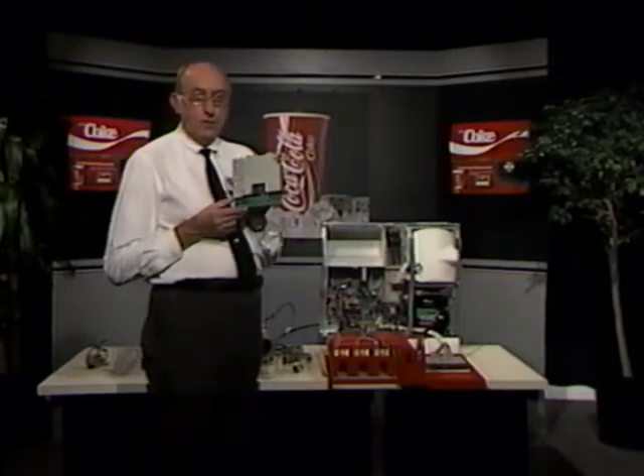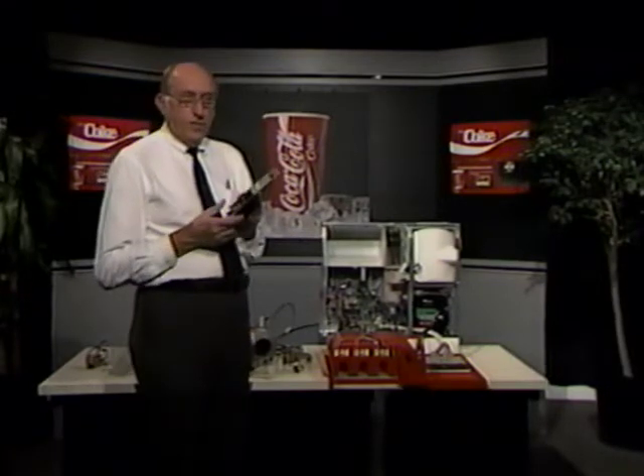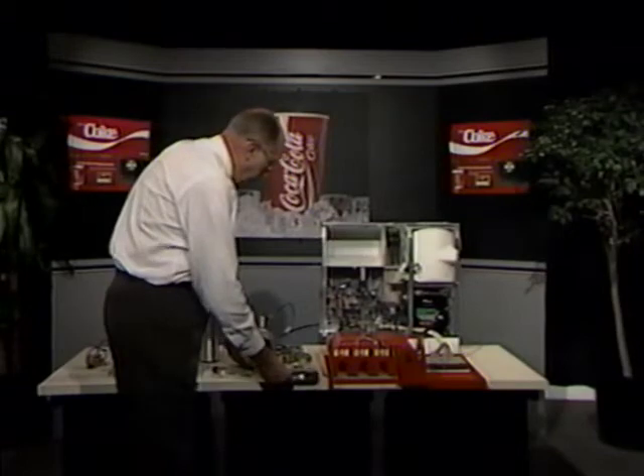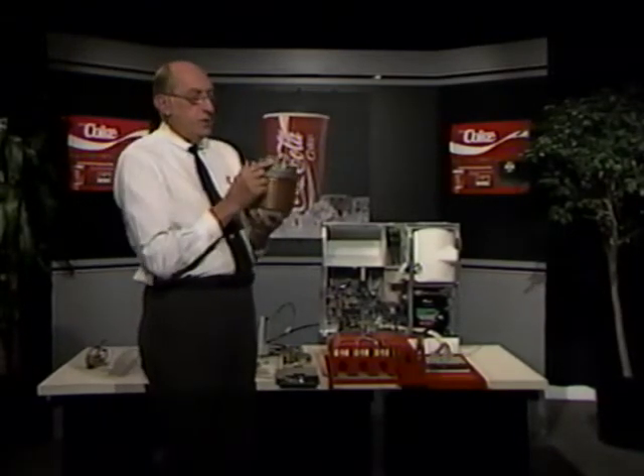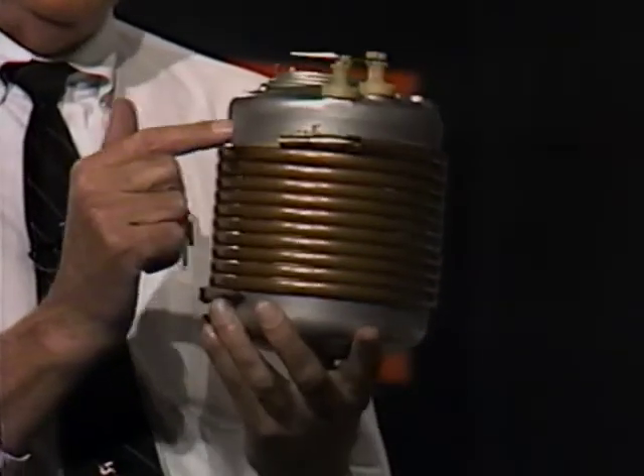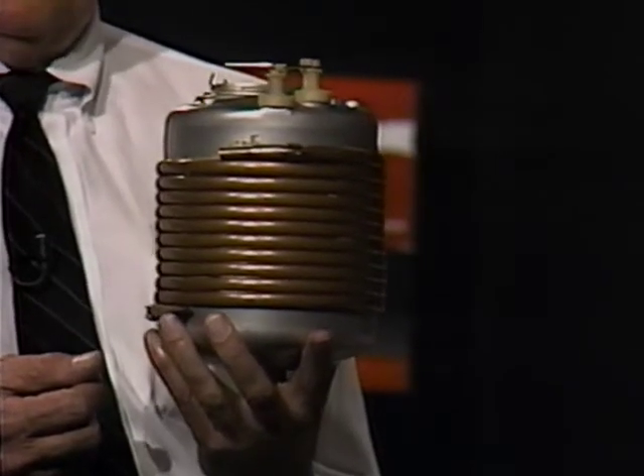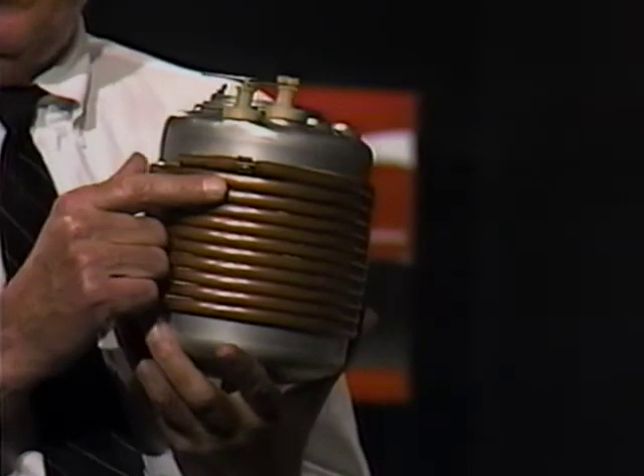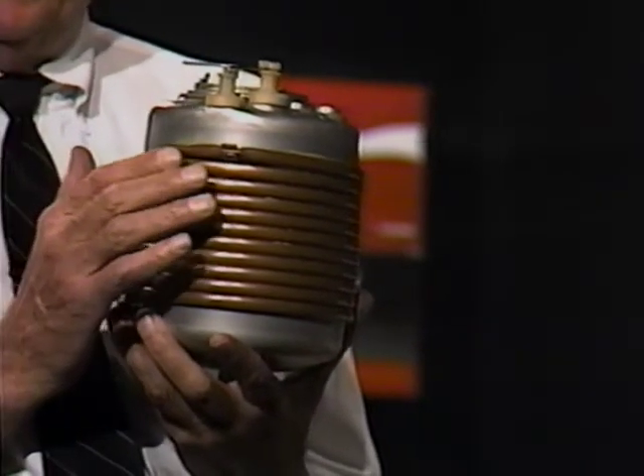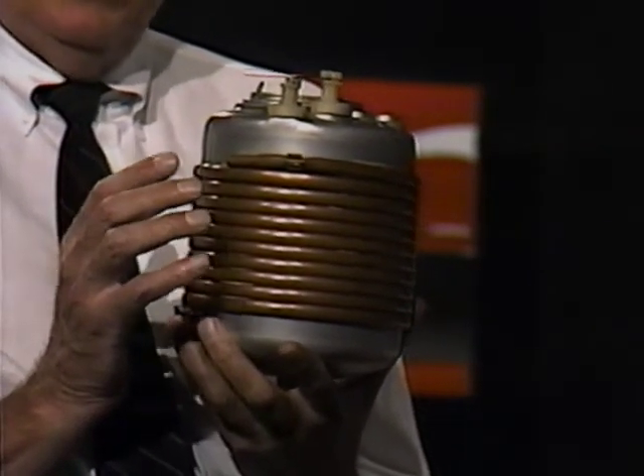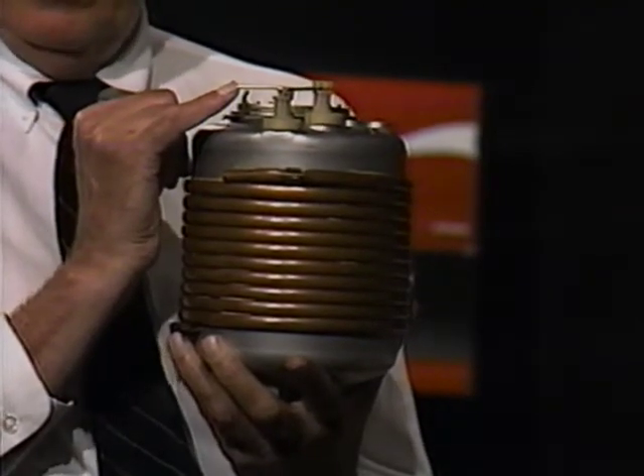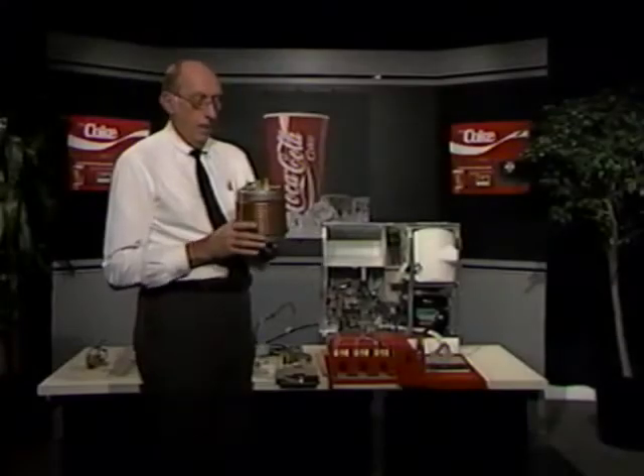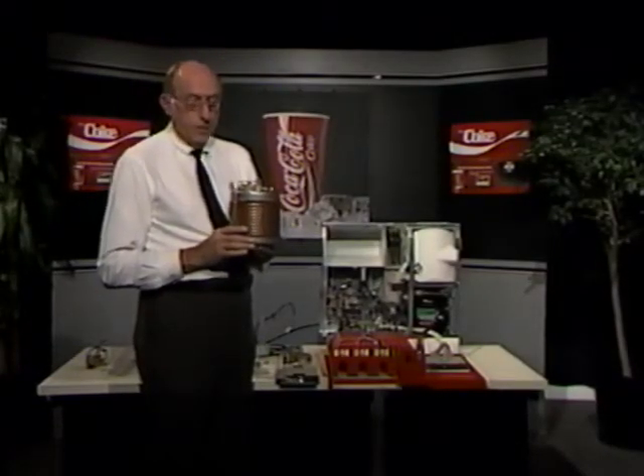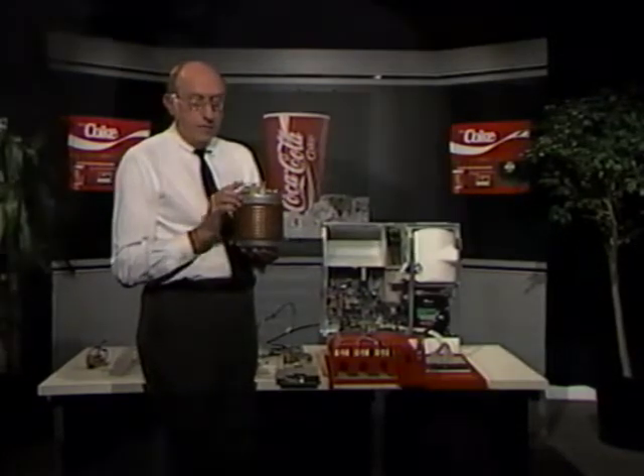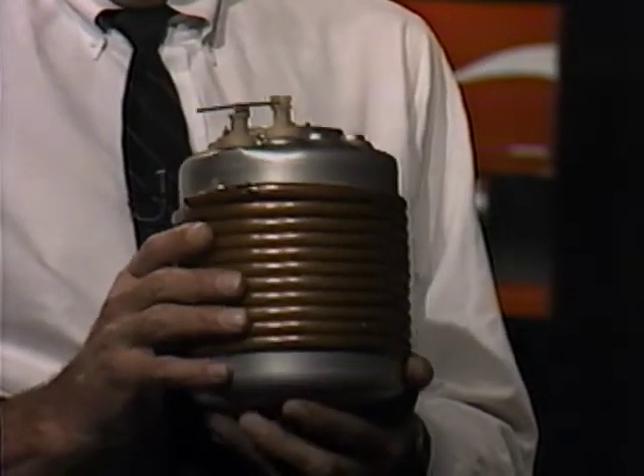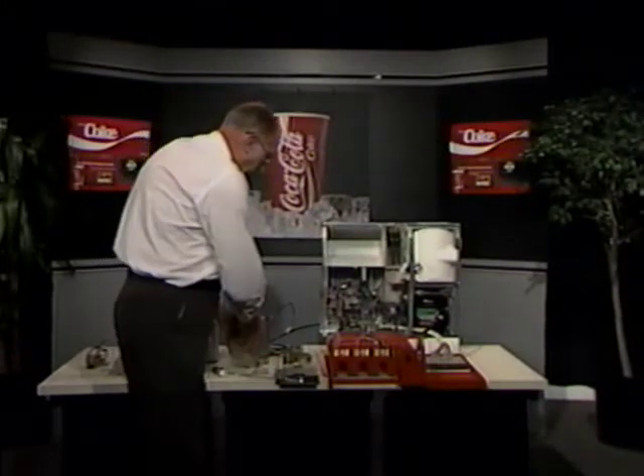The ECM board controls the refrigeration, and it controls it from 2 sets of sensors. One set of sensors is the electrode in the carbonator, which senses whether or not there is an ice bank touching the electrode. Just the tip of the electrode is exposed to water in the carbonator, and when the water freezes in that area, when the ice bank is formed, the ice is an electrical insulator and stops the tiny sensing current from going through the electrode. So the ECM board picks up the signal and shuts off the refrigeration. Or in the case of the carbonator, when the electrode's covered, it transfers the refrigeration to the syrup compartment through the syrup transfer valve.